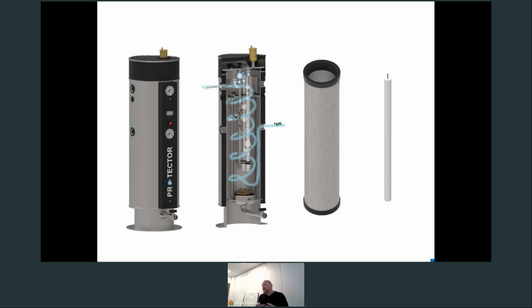But VDI demands that you have the anodes encapsulated, and on existing systems, that is a mesh that sits around the anode, more localized. And the issue we have with that is that inevitably, when we replace the anodes, you've still got a lot of magnesium left within there that's not being used. So having that basket sitting within the system, which creates that encapsulation, and having the separate anodes unsheathed, allows us to burn right down to the wire. So you've got no waste happening within that system.